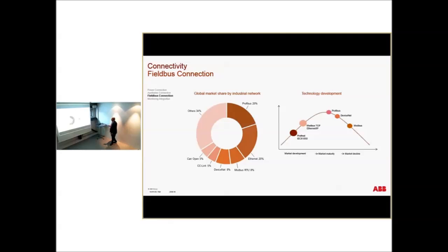Again, this is the situation of the communication. At the moment, I put just the main ones. You have Modbus, which is the present one used by main breaker manufacturers. Then you have Profibus, used by one manufacturer, and DeviceNet by the American one, but this is the future. Also, what has been done, we decided to still accommodate these three, plus look after this new one. So this is the global market situation. Profibus is more or less the leader. Modbus is decreasing, but this one is what will become available.